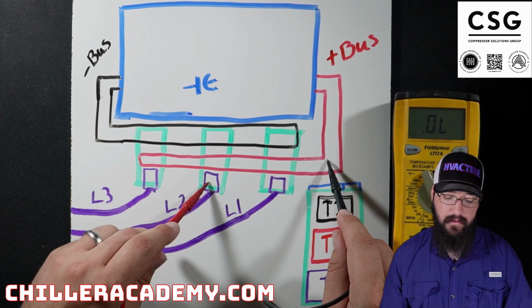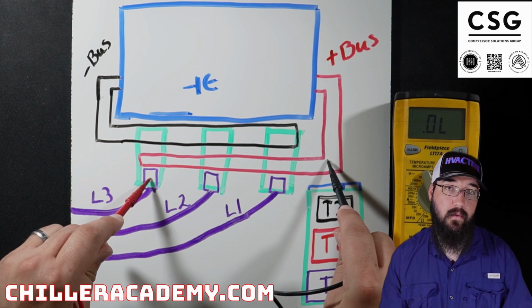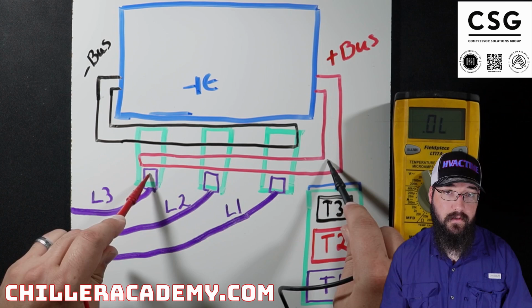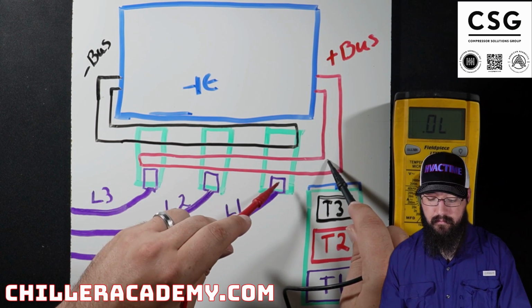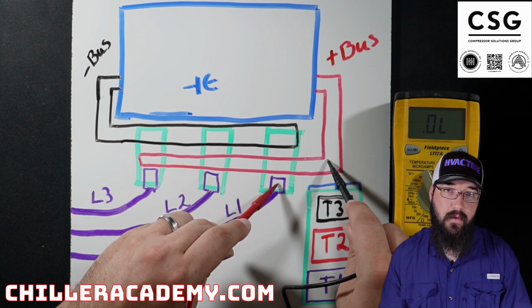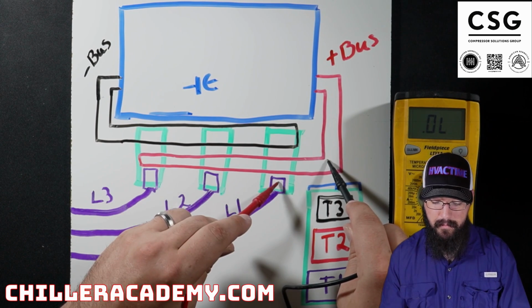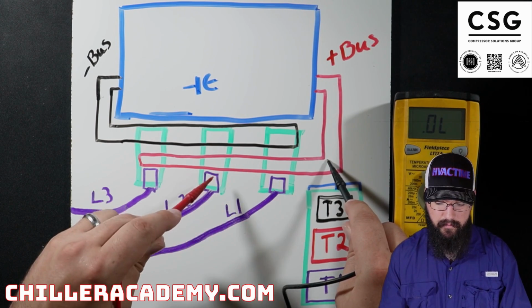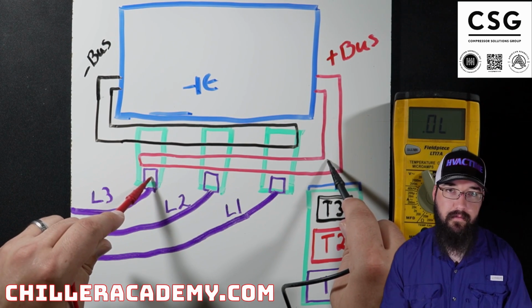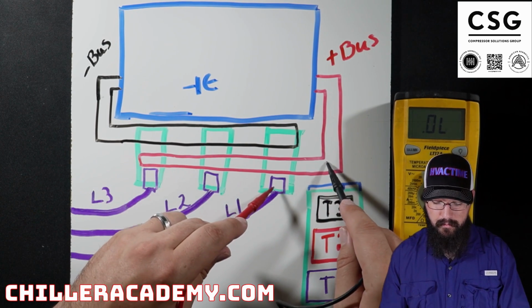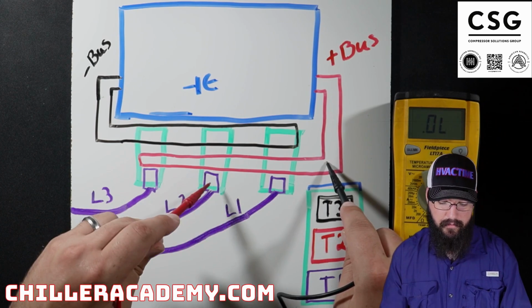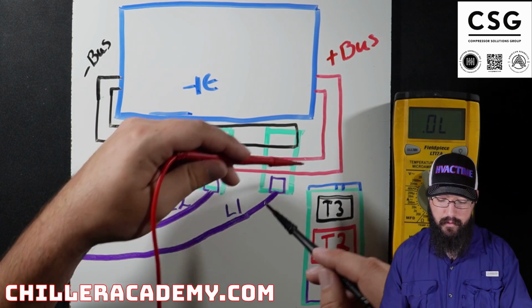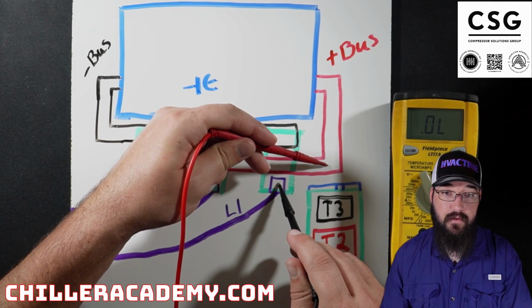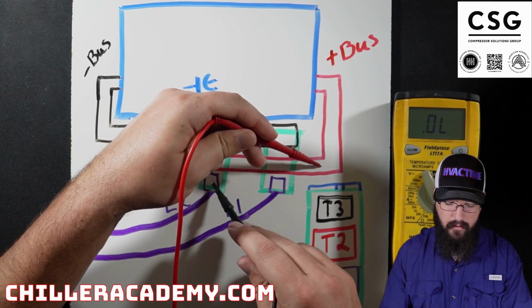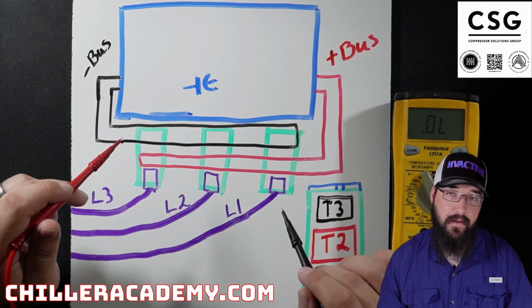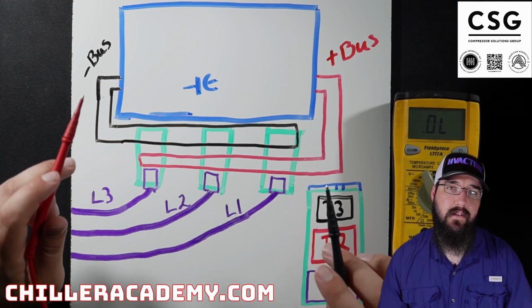And then as you step through this test, you're just going to go across each T1 terminal. You should get the same results across each of these. By same results, I don't mean 2.5, 2.5. What I mean is this one may be 2.5, 2.6, 2.5 again, but you shouldn't be getting a 2.5, OL, 2.6. And then when you reverse your leads, if this gives you OL, then you would want to see OL and OL.